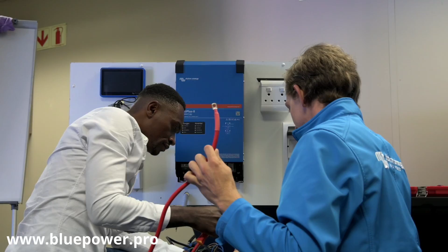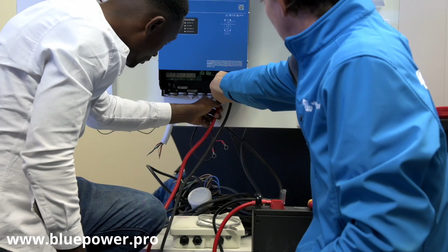Yeah, it's going to be bigger. It's going to be like this. So if you've got a 6mm nut, make sure you put on a 6mm lug as well. It's important. Those studs, yeah. And then on the washer and spring washer, it's recommended you put your lug onto the connection, then your washer, and then your spring washer. So make sure that that's also the right way around, and then we can put our nut back. We don't want anything between the connection and the lug, as that is going to cause hot connections.